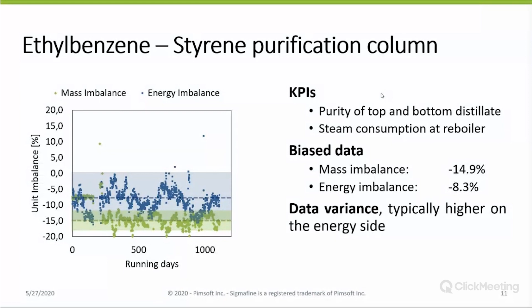Moreover, there was not only a relevant imbalance in the data, but also quite a large data variance, especially affecting the energy side. So the goal here was to get rid of such imbalance and have accurate KPIs regarding the steam consumption at the reboiler of this column, and compare the steam consumption against the purity of the distillate at the top and bottom, which are the main values checked by operators to stay in specification.